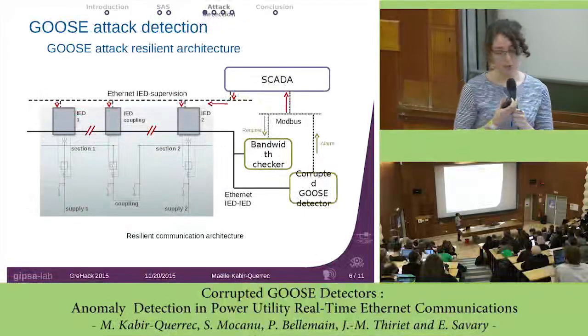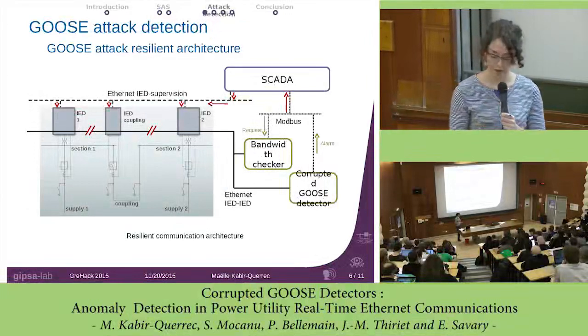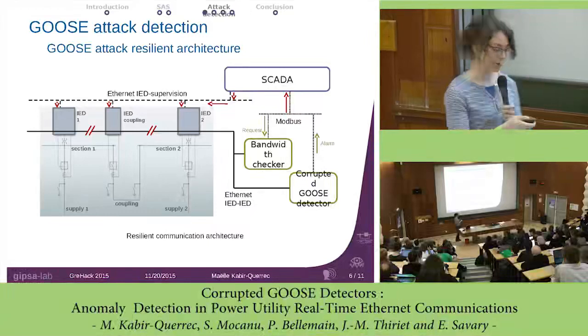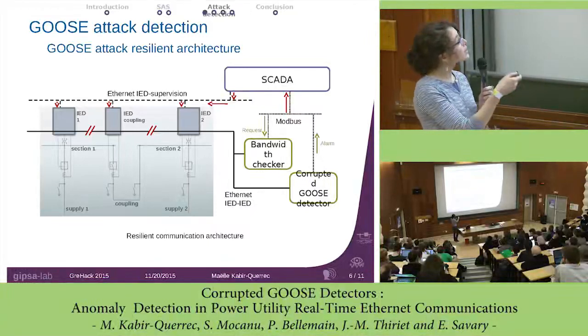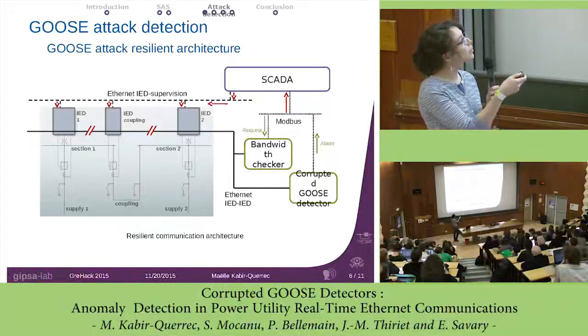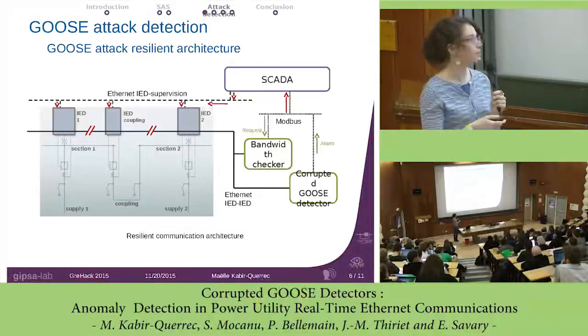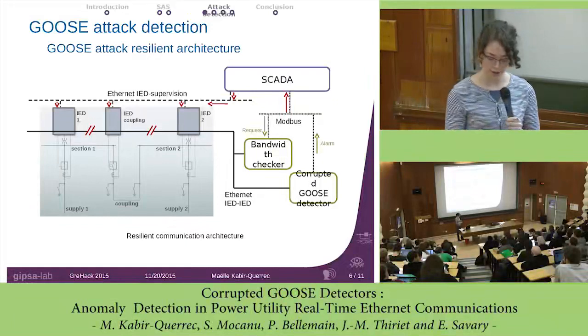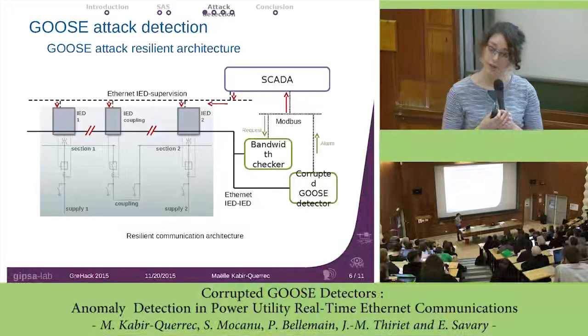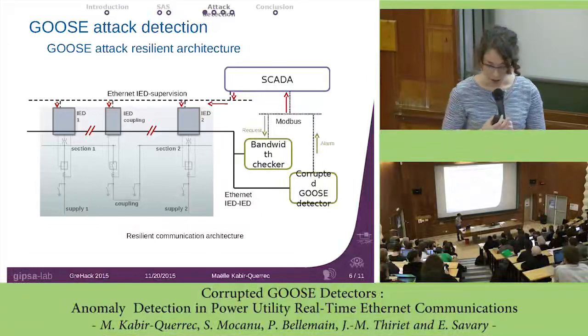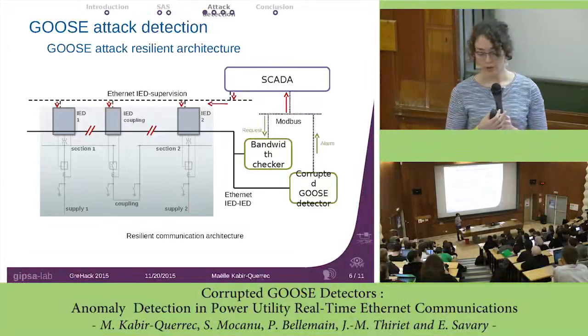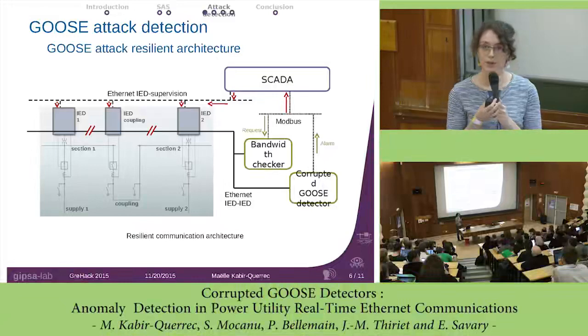Here is the communication architecture. It's basically the same as two slides back. You have your process, your IEDs, that is Intelligent Electronic Devices. You have the Ethernet IED supervision link. So here is IED supervision communication. And you have this Ethernet link for GOOSE protocol. So that is IED to IED communication. And on this communication architecture, we added our detectors, which I will detail a bit later. We added a module to check the bandwidth, to verify there is no Ethernet storm. And we added a module to detect corrupted GOOSE messages.